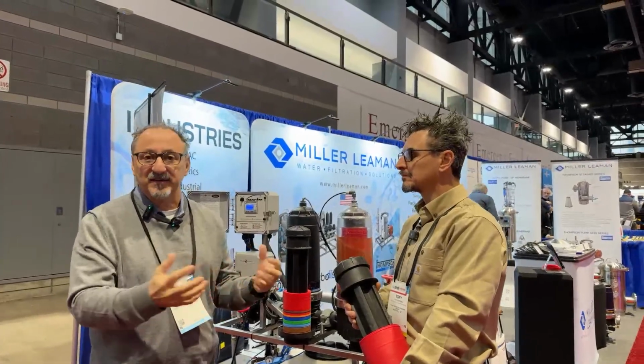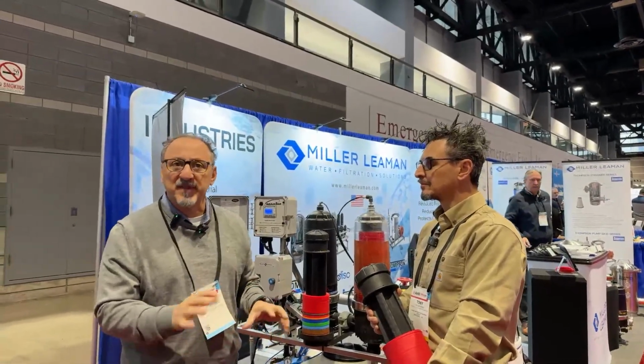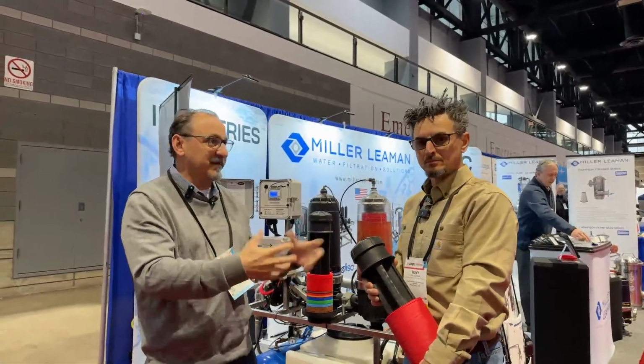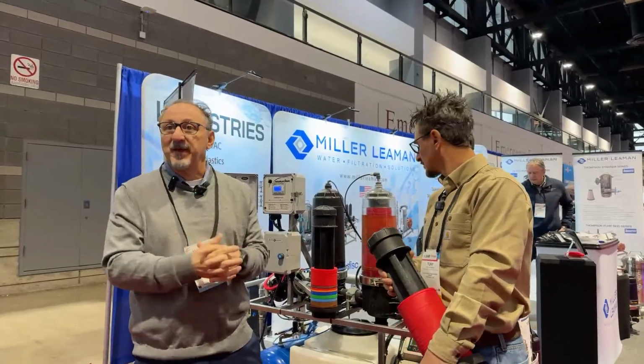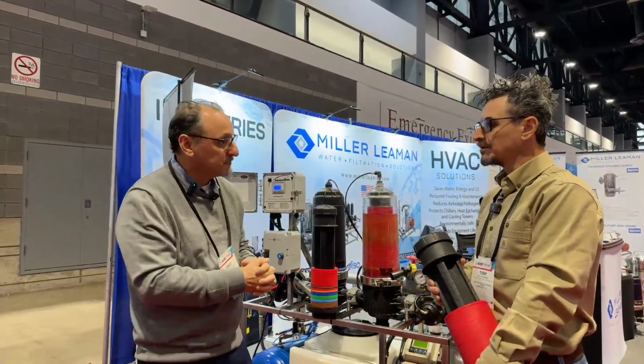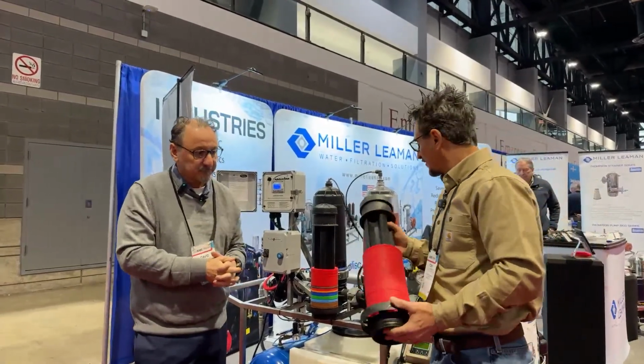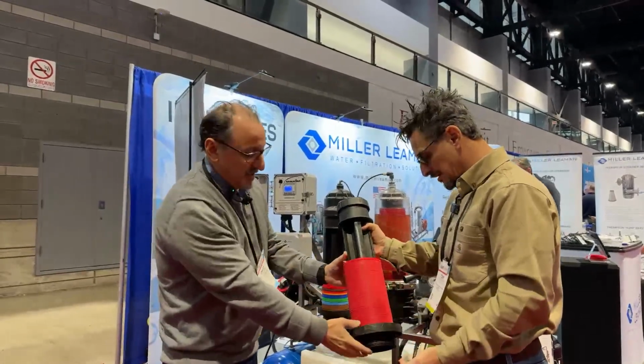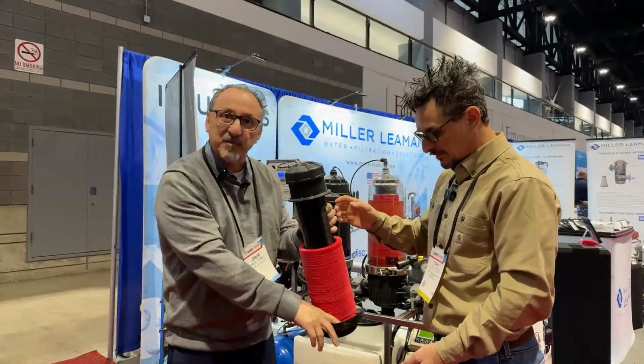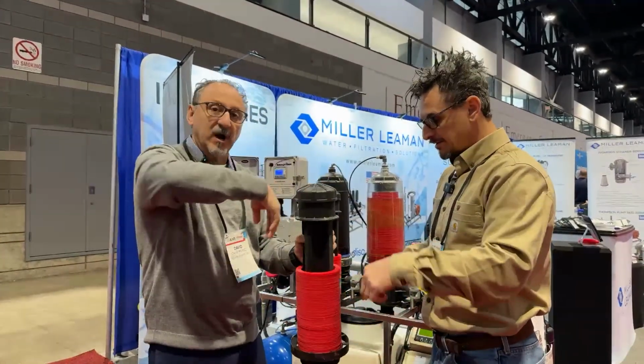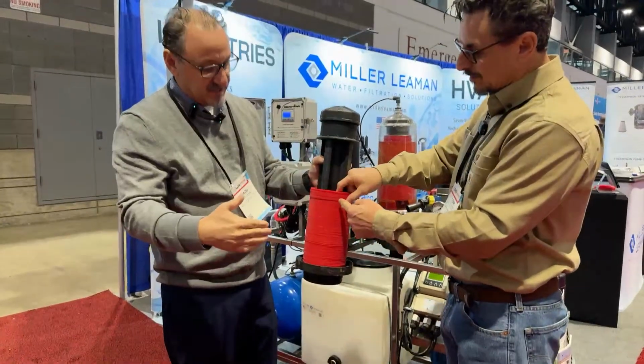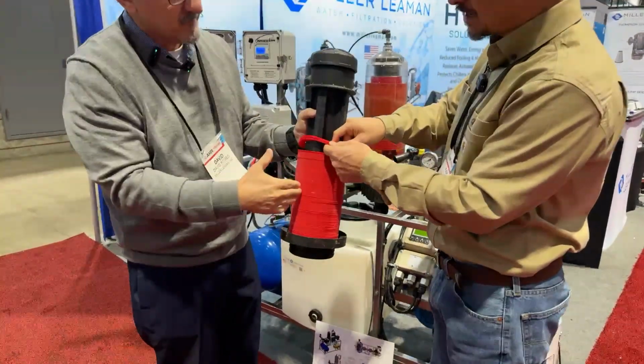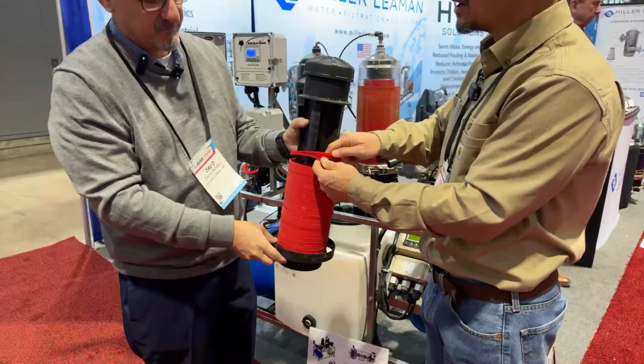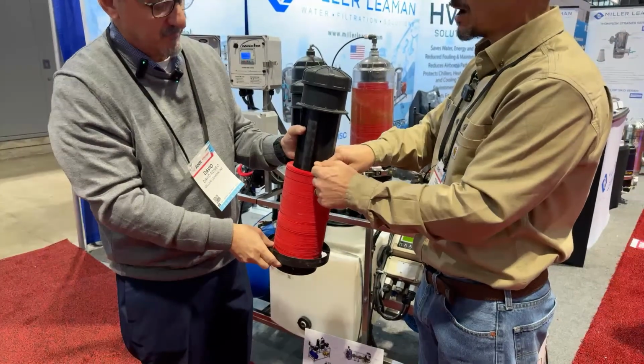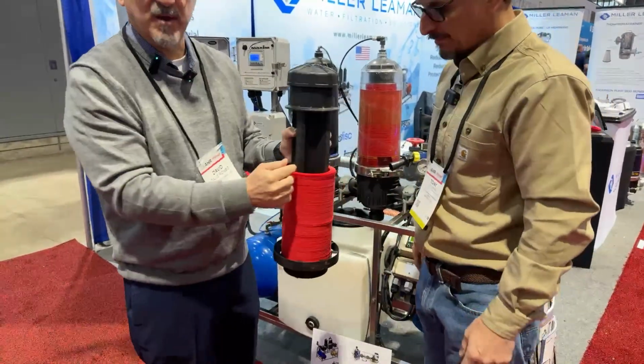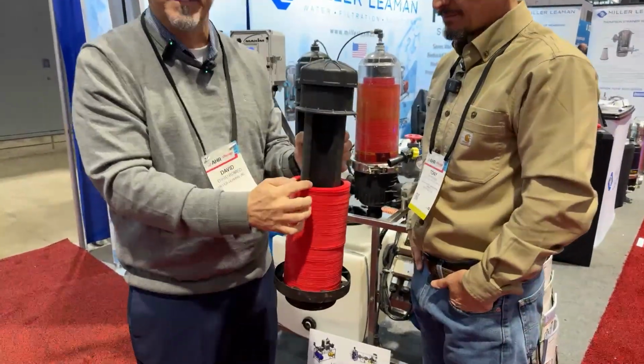So you're taking, say, a 1,000-ton cooling tower, which flows around 3,000 gallons per minute. We take 10%. It would be around a 300 GPM side stream system. Nice. And refresh my memory. The water comes in through this helix effect, which is right here. Right here. Spins the water. It goes through these discs from the outside, through here, and then you can't see it on the screen probably, but there are little grooves in here. That's where the water goes through and it traps the particulates. Traps the particulate. Okay. It polishes the water. That's where you get your depth right there.